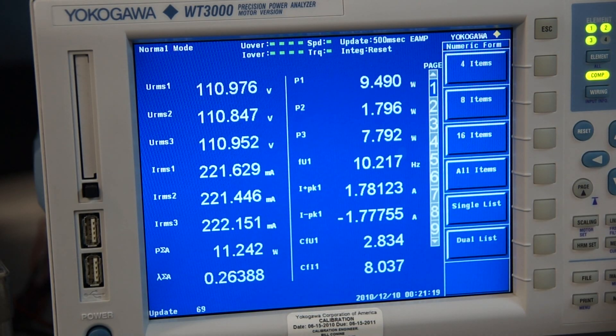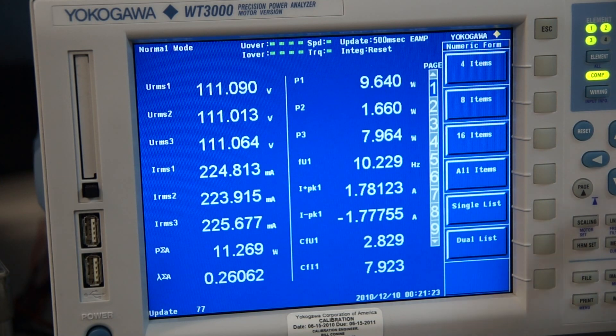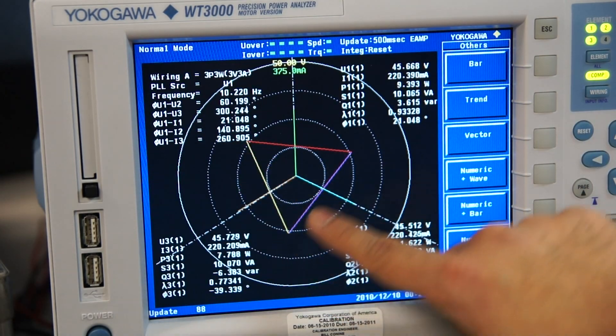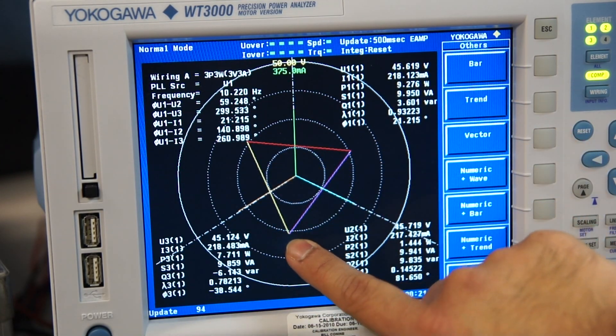Now another way you can verify on the power analyzer if your wiring is correct is you go back to the vector display on this meter, and you should be able to see your delta connection on your voltage, which is what we see here.